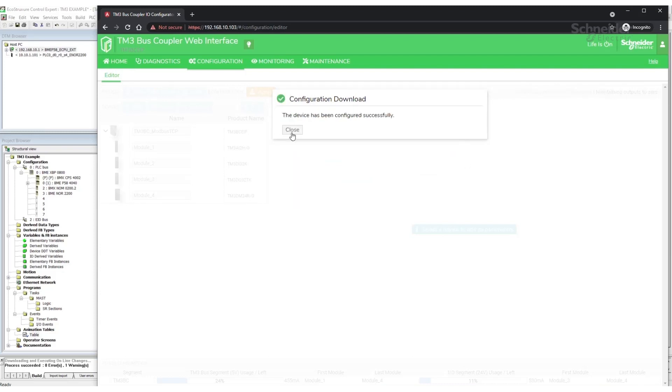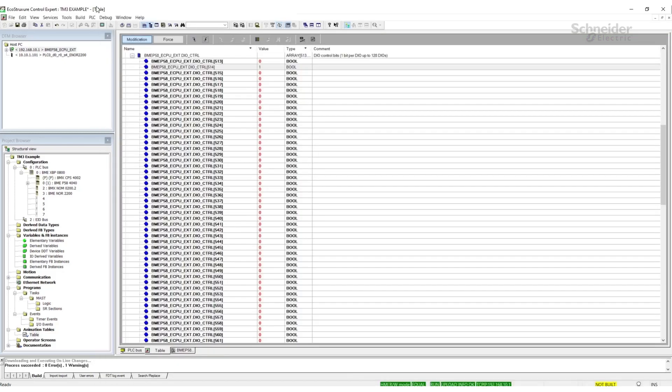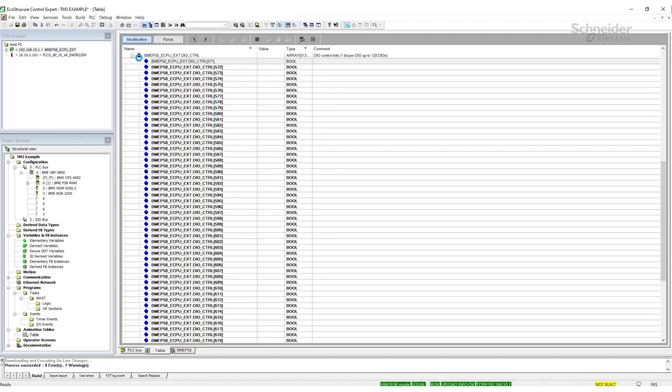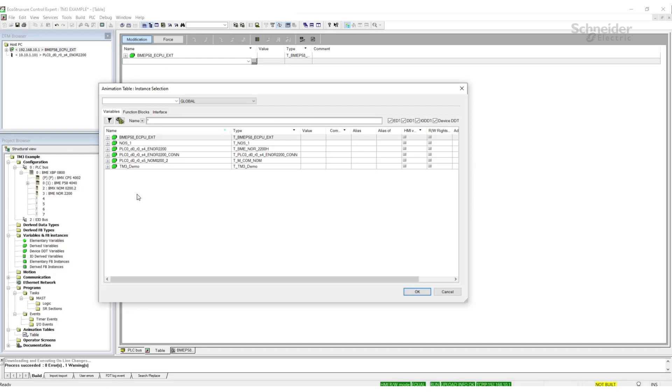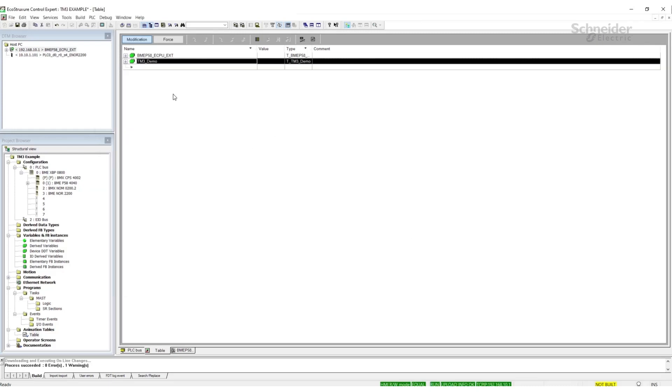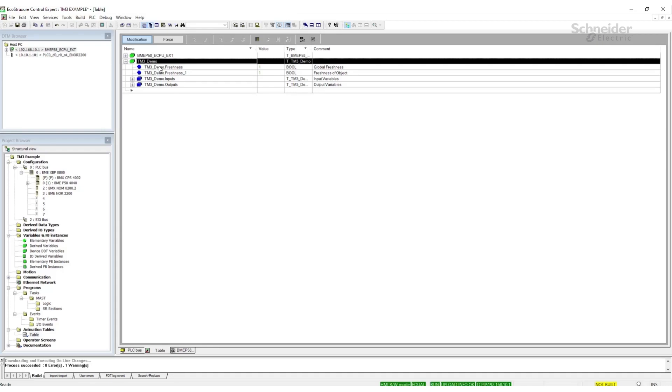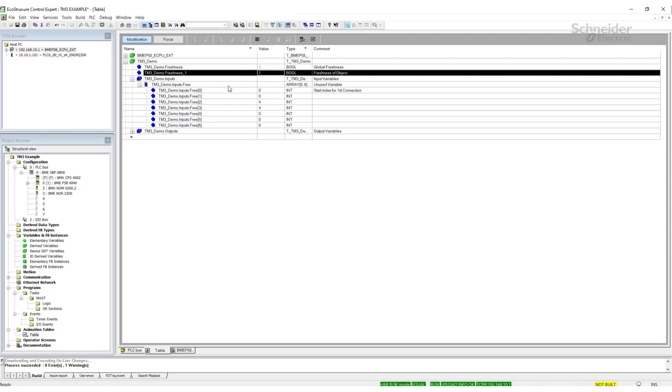Now that it's downloaded successfully, we can come back to the M580 program, re-enable the communications. To verify it is communicating, we can now add the DTM for the bus coupler. Find the name that you created, add it to the animation table, and the freshness should have a 1, indicating that we are actively communicating. Any data from the bus coupler will be populated inside the DTM in the configured arrays.